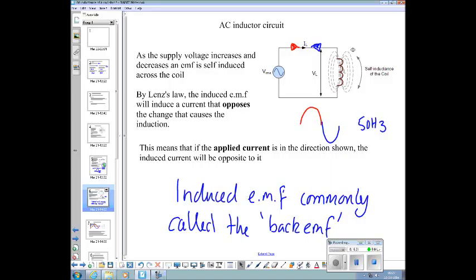When you start a motor, how many of you work in an area where you've got lots of motors? When you start a motor, you'll be familiar that you get high current, and then that falls back. Part of that is down to once it gets spinning, it's creating its own back EMF that restricts the current. Initially, you've got a very low resistance coil that you're putting 400 volts onto, the ammeter goes way over, and then the motor starts to spin, creates its own back EMF and restricts that current back. So that's part of the reason for that.